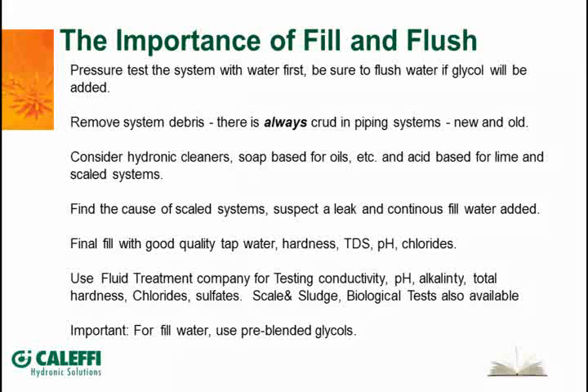So if you don't have good quality water on the job, you've got a hardness test kit. You can test some of that on your own. Bring the water in with you. It's easy to find conditioned water. Even here in Springfield, Missouri, a town with a population of about 150,000 people, there are three different companies locally that will sell me water. It's called deionized water, demineralized water, where they run it through a resin bed and it can scrub away a lot of those problems before you put that water in. I just take a 50-gallon plastic barrel down there and they fill it up right on my truck, and then I can take that to the job and just pump it in.